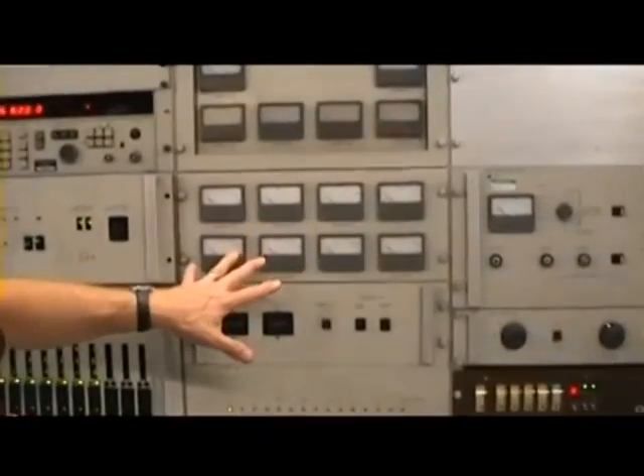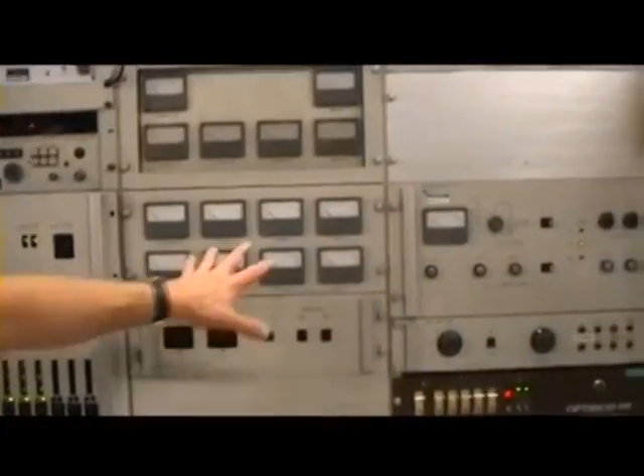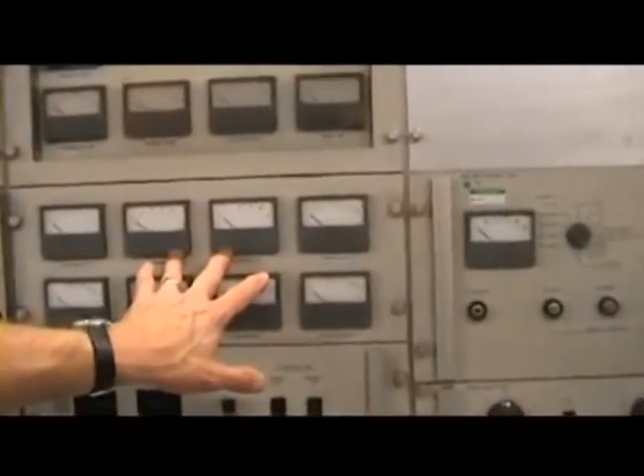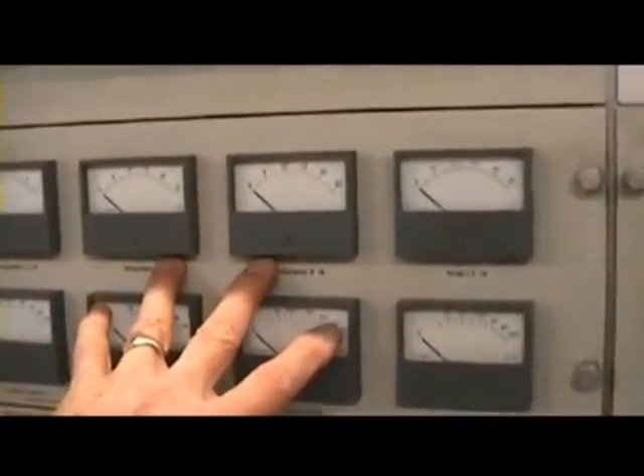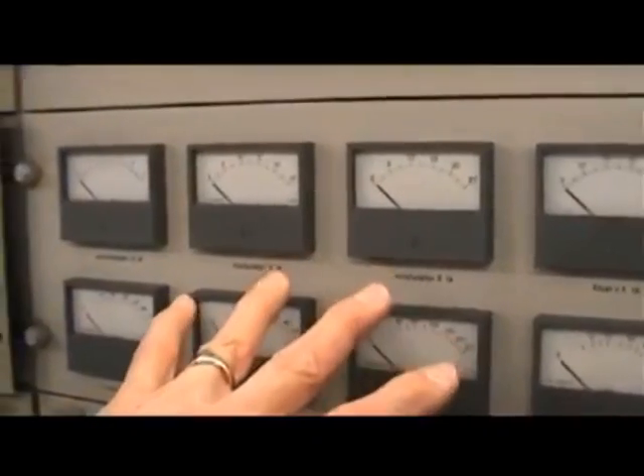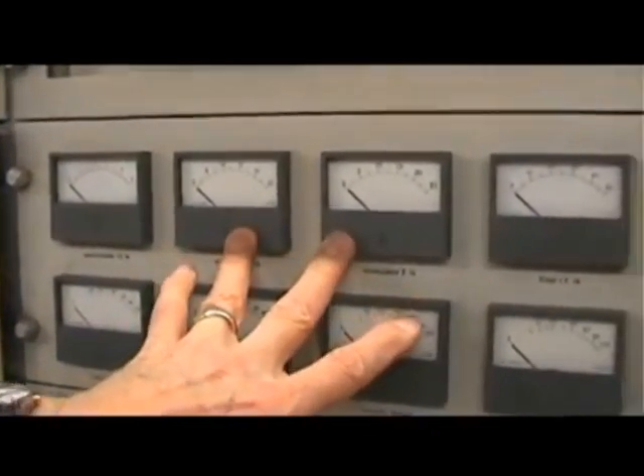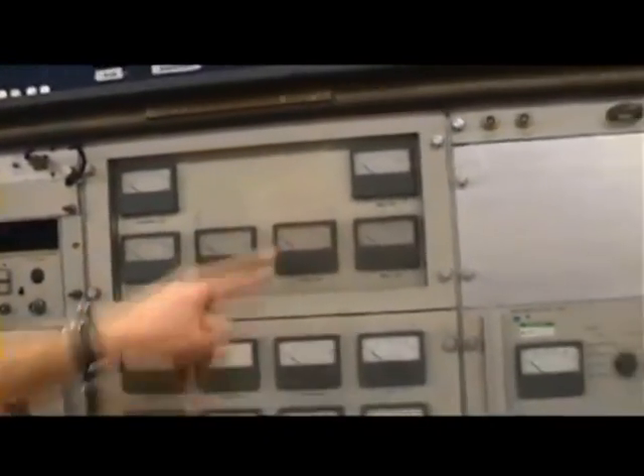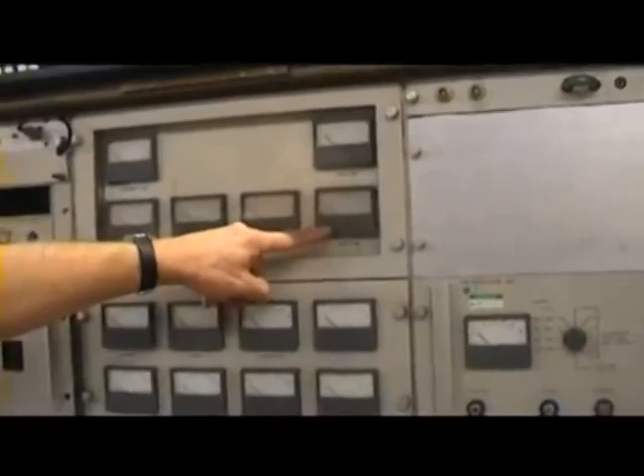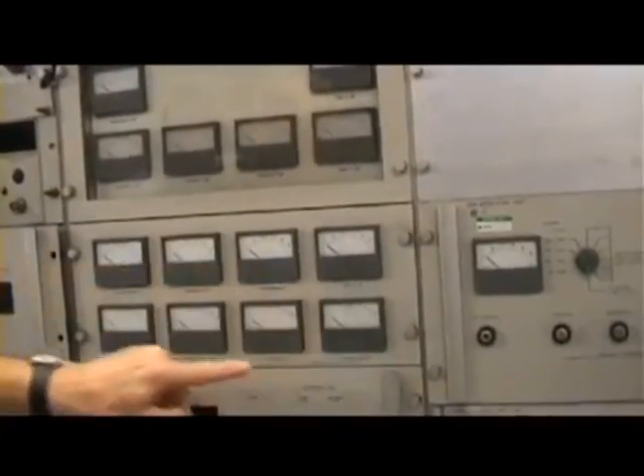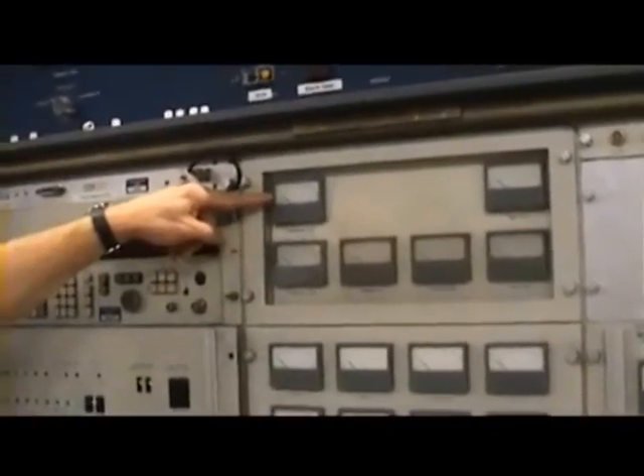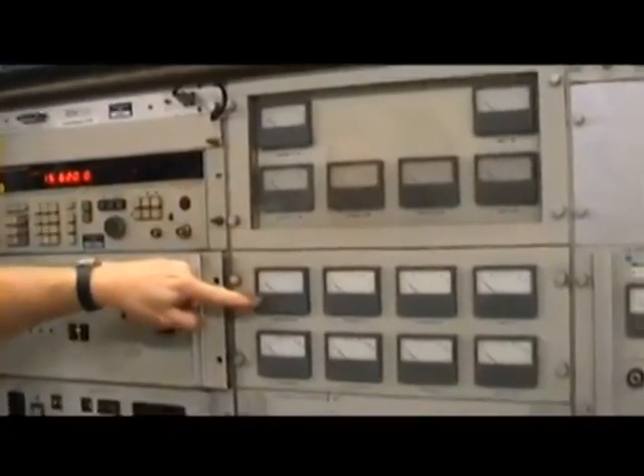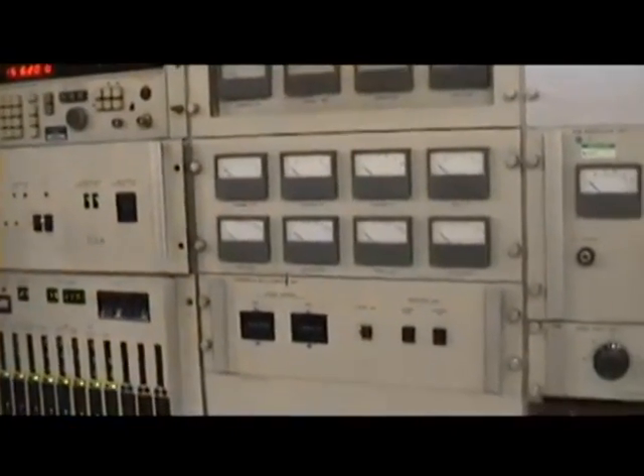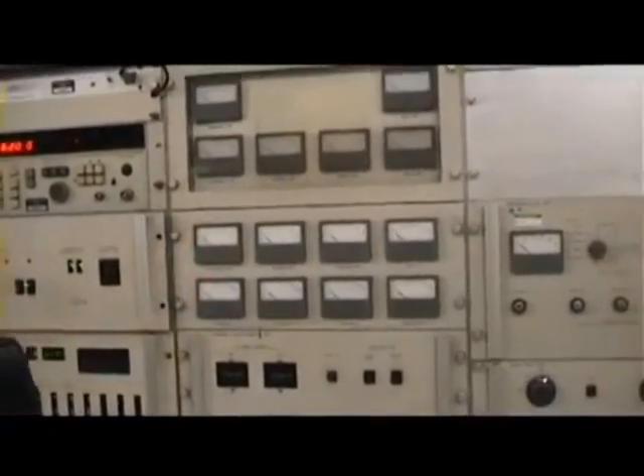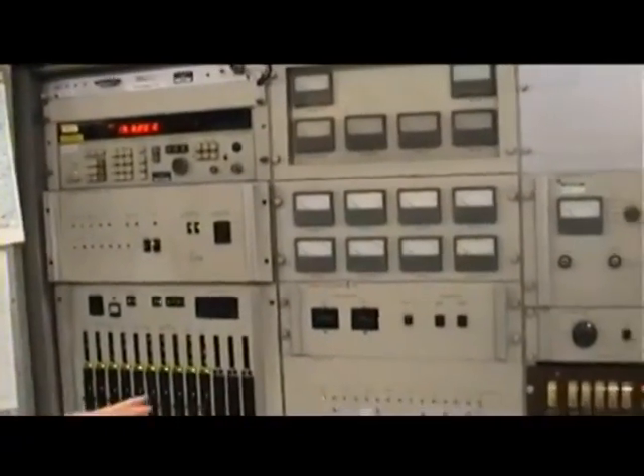Analog metering is provided. High level class B mod, or AB, it's in AB1, so grid current doesn't flow on the modulator tubes. They're around the corner, we'll have a look at those in a minute. So you've got the modulators here, and you've got the RF section metering sort of round the edge. Grid current, screen grid current, cathode current. Penultimate stage as well has got grid current, screen grid current, cathode current. We'll have a look at one of these working on a later shot.